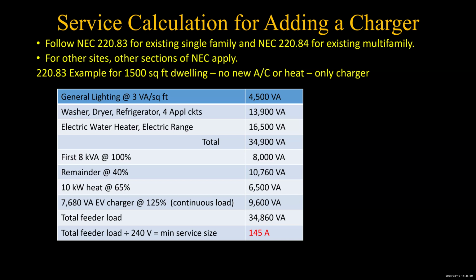And if we're adding, we can take the first 8 kVA at 100% and the remainder at 40%. And then we haven't talked about the heat or the air conditioning yet. Since they're non-coincident, if the heat load is bigger than the air conditioning, then that's going to be 6,500 volt amps.